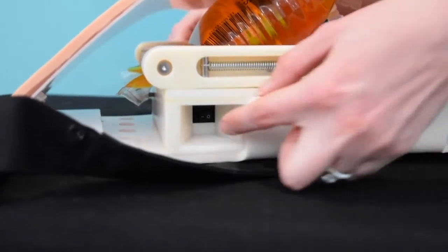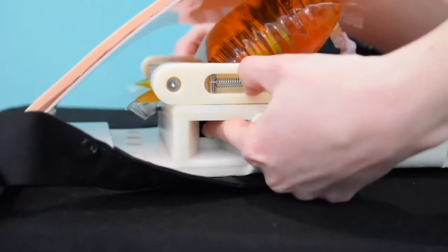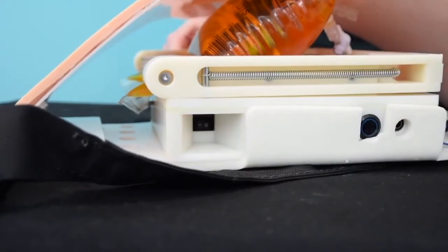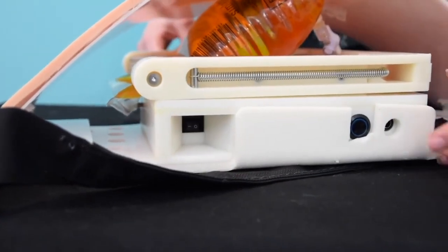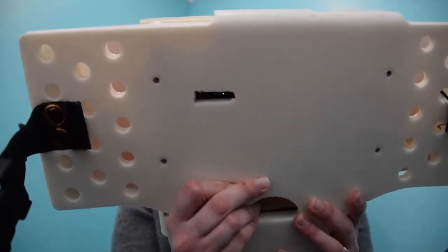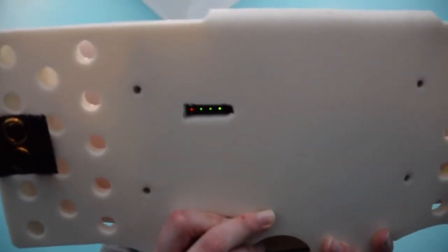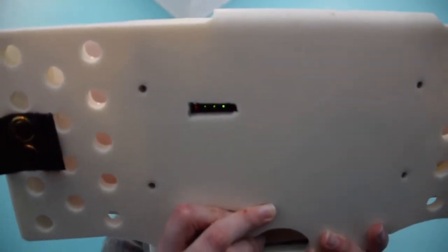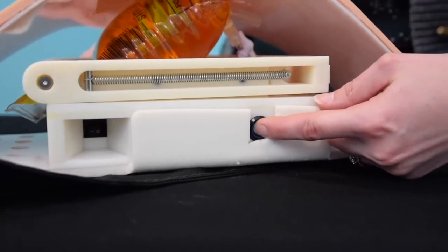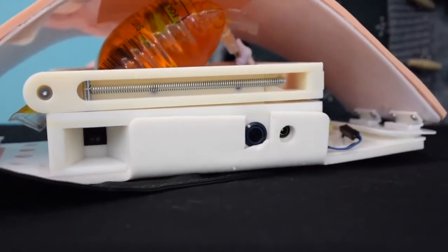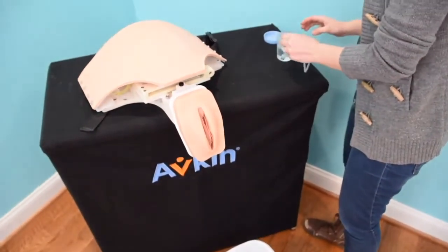Now we can prime the device to get fluid through the system. To do this, we are first going to turn the device on using the switch on the back of the device. There is also a battery indicator underneath the device to tell us how much battery we have left. Then we are going to press the priming switch and hold it for about 4 seconds, which will allow fluid to run through the system.